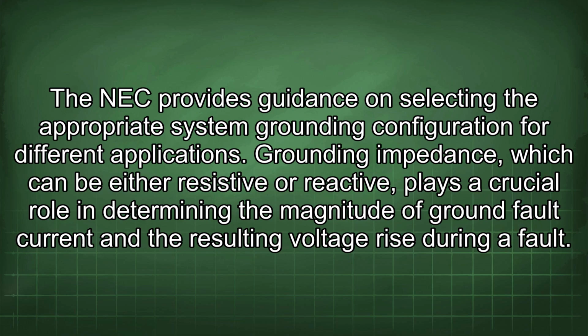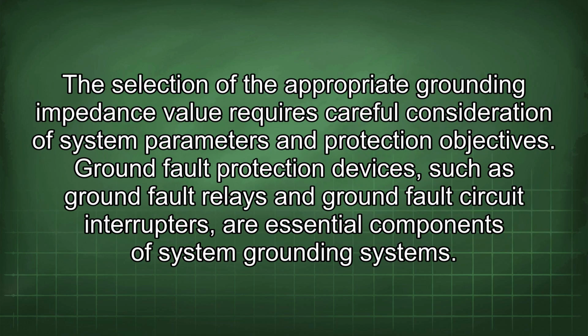Grounding impedance, which can be either resistive or reactive, plays a crucial role in determining the magnitude of ground fault current and the resulting voltage rise during a fault. The selection of the appropriate grounding impedance value requires careful consideration of system parameters and protection objectives.